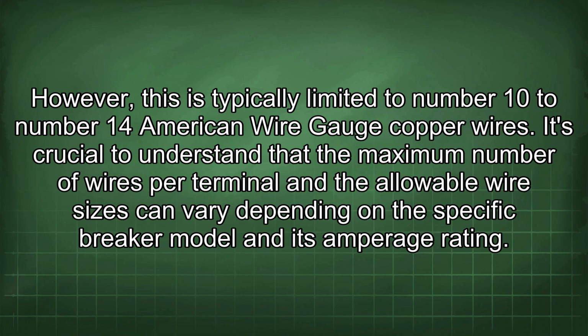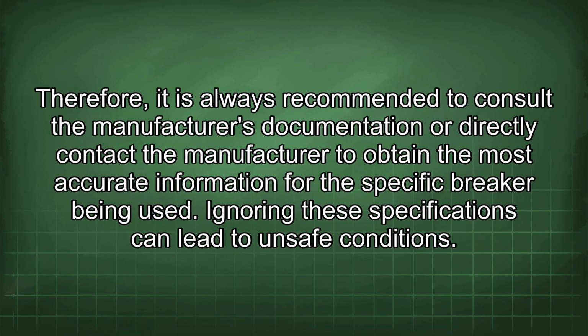It's crucial to understand that the maximum number of wires per terminal and the allowable wire sizes can vary depending on the specific breaker model and its amperage rating. Therefore, it is always recommended to consult the manufacturer's documentation or directly contact the manufacturer to obtain the most accurate information for the specific breaker being used. Ignoring these specifications can lead to unsafe conditions.